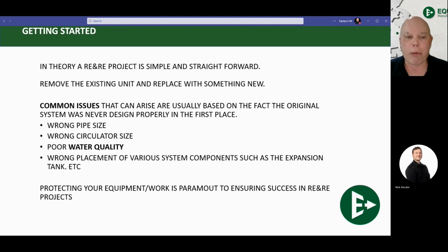If you find your water is black or brown, you have poor water quality. You're going to have a tremendous amount of what's called total dissolved solids or particulates in the system, which is going to be impeding the heat transfer from your radiators or radiant in-floor PEX tubes or copper pipes inside of your air handler. If you have dirt inside of that system, poor water quality is going to lead to a premature failure of our heat exchangers and not enough heat transfer through our heat emitters. Water quality is something that needs to be addressed before you put a new boiler into a system. Otherwise, the problems that you created yesterday are going to follow you to tomorrow, even with a brand new system. So addressing water quality is something that you want to make sure you get done and taken care of.